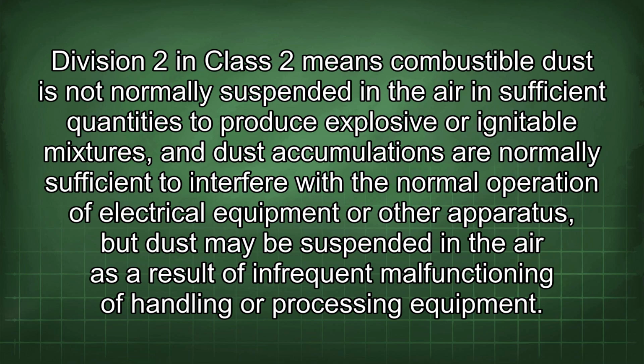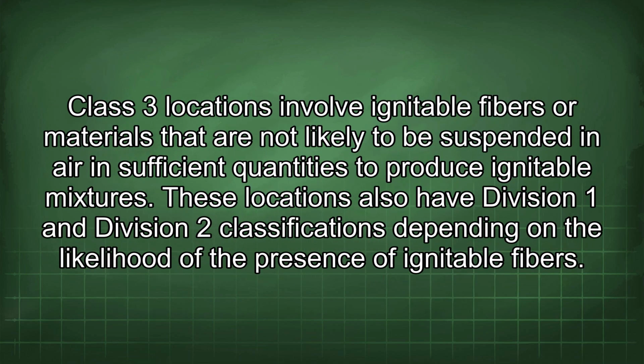Division 2 in Class 2 means combustible dust is not normally suspended in the air in sufficient quantities to produce explosive or ignitable mixtures, and dust accumulations are normally sufficient to interfere with the normal operation of electrical equipment or other apparatus, but dust may be suspended in the air as a result of infrequent malfunctioning of handling or processing equipment. Class 3 locations involve ignitable fibers or materials that are not likely to be suspended in air in sufficient quantities to produce ignitable mixtures. These locations also have Division 1 and Division 2 classifications depending on the likelihood of the presence of ignitable fibers.